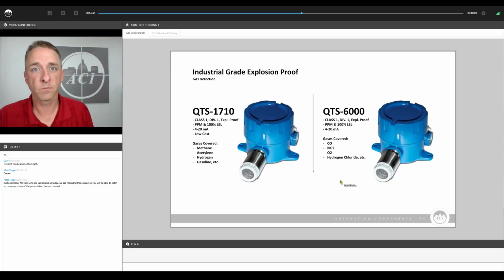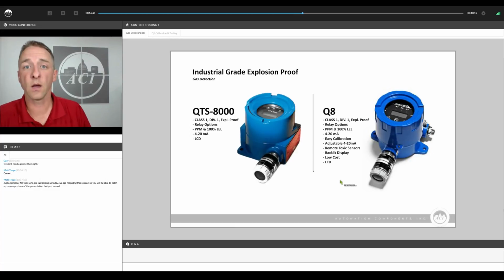We have also these versions available with LCD and some additional communicating features. The QTS 8000 and the Q8 again are both in Class 1 Div 1 explosion-proof rated enclosures. They have relay outputs. They can be programmed for either a parts per million output or a percentage of the lower explosive limit, so you can configure which output you want or which is required. You can do an analog 4 to 20 output or an LCD or the relay outputs, and these are all configurable through the LCD units on the screen.